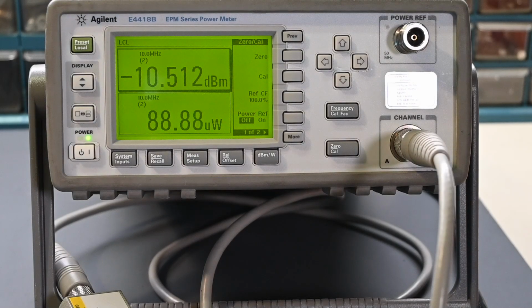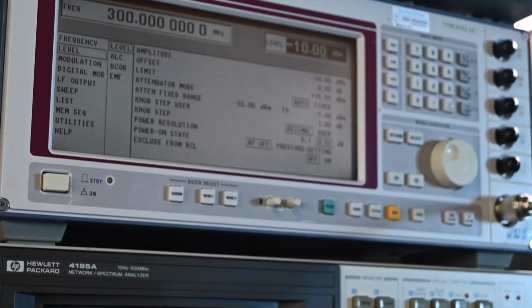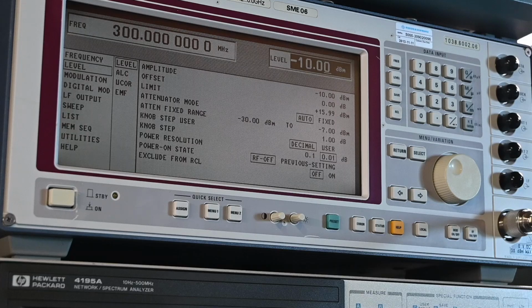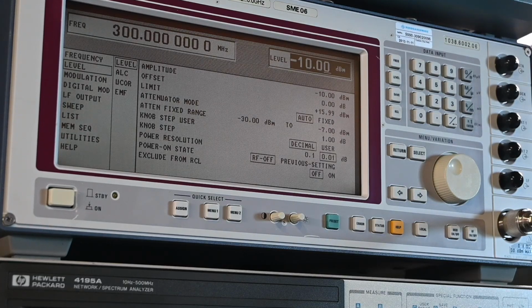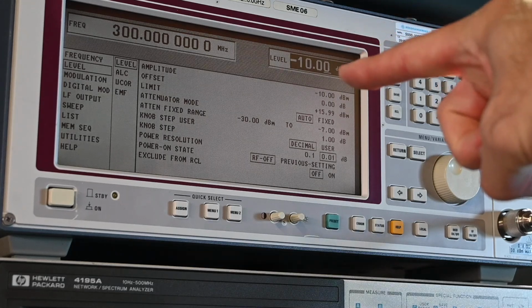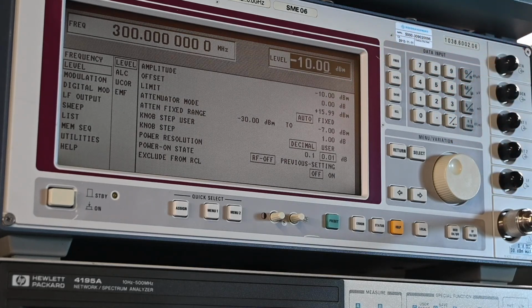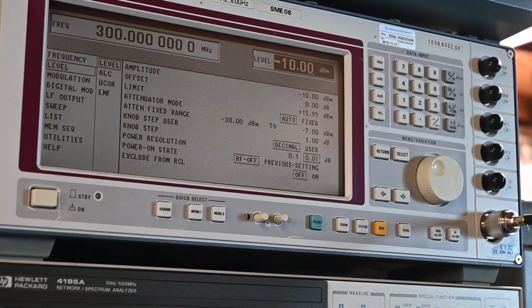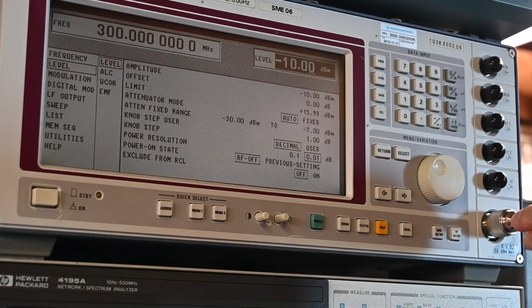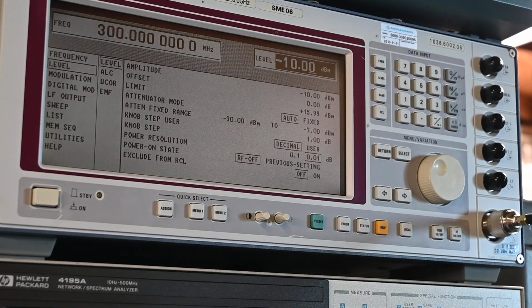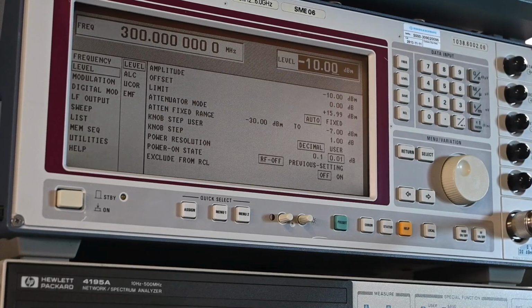Now, let me just move this over here. Pardon the camera movement. I'm just going to swing this over to the signal generator just this one time so you can see the setup over here. Pardon all the movement. So that's the SME06, and you can see that right up here, right there is the output level, so you can see it's set to minus 10 dBm. And if that power sensor were connected to the output of the signal generator, move this over just a little bit more, so you can see right over here is the output cable. If that power sensor were connected right there, it would be reading minus 10 dBm. This is a very accurate output on the signal generator. But again, we have some loss in that coax. So let me move this back around over here. Pardon the camera movement. Just swing this back around.